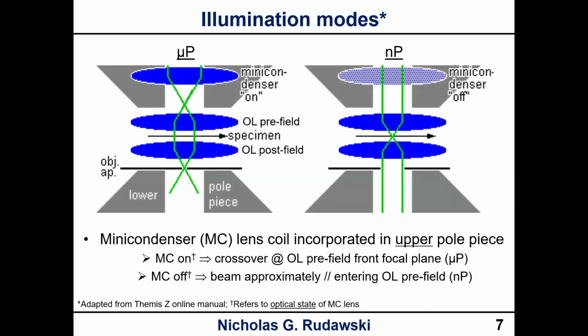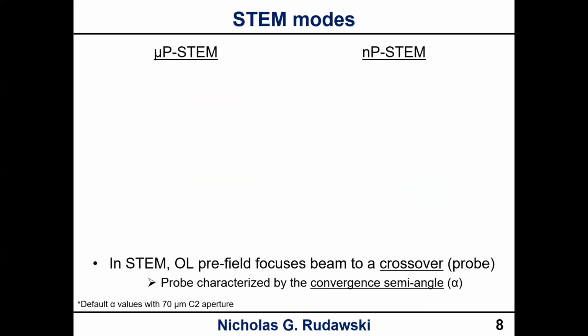So it took me a little while to wrap my head around this, but there's a difference between the lens being off physically and being off optically. The reason you don't want to turn the lens off completely is because you have a temperature change when you do that, because you're no longer putting current through the coil. And so that introduces things like thermal drift. It's better if you turn it off optically, and you don't have that issue as much. So it's important to note that difference. When we turn the mini condenser lens off, that's optically off, not actually physically cutting the current to the coil.